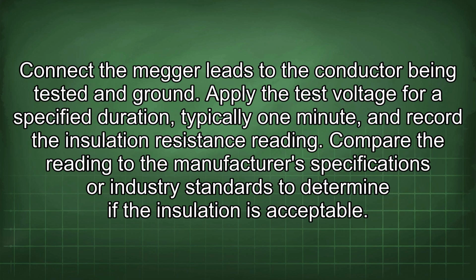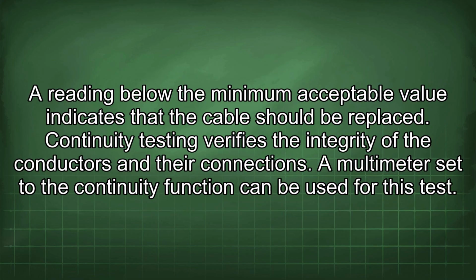Connect the megger leads to the conductor being tested and ground. Apply the test voltage for a specified duration, typically 1 minute, and record the insulation resistance reading. Compare the reading to the manufacturer's specifications or industry standards to determine if the insulation is acceptable. A reading below the minimum acceptable value indicates that the cable should be replaced.